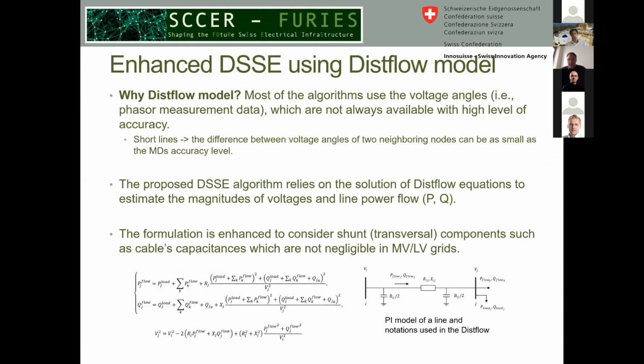For DSSE, for state estimation, what we proposed is a DSSE based on the dist flow model. Why dist flow? Because with the available measurement devices, we do have access to voltage magnitude measurements and power flow measurements, but we do not have access to the voltage angles with enough accuracy.